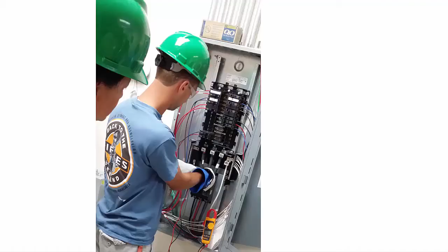Step 13 requires personal protective equipment. We will measure the AC volts on our circuit breaker at the electrical subpanel. Before we begin, we make a prediction. Our prediction is that our volts will be the expected voltage for our building. Here we have another picture of a former participant, this time taking the volts at the electrical subpanel. Our prediction was to get roughly a measurement at the expected voltage for our building. At our Commercial Avenue campus, that's about 208 volts. Let's take a closer look at this.